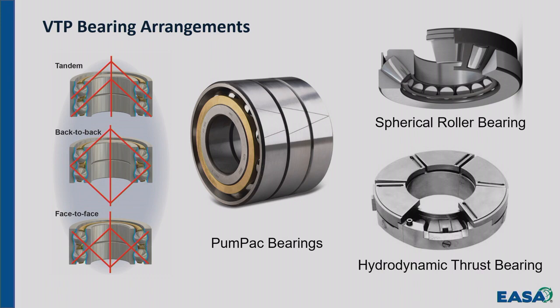If the motor was taken off of the pump and sent in for repair, and the person who did the disassembly very carefully noted the configuration of the bearings, and they're certain that they were put back in the same way, and that motor went back onto the same pump, you probably won't have any problems. But I think I used the word if. I thought I used that word, okay?